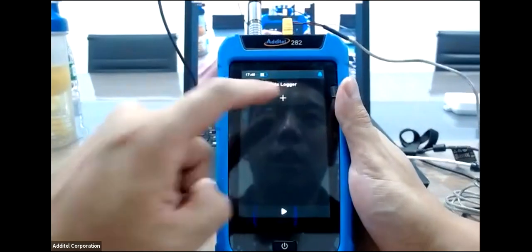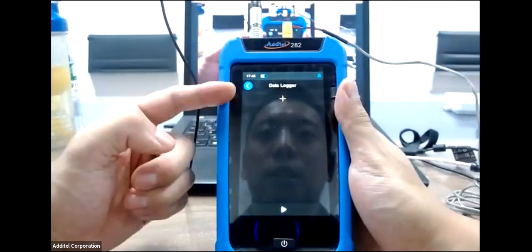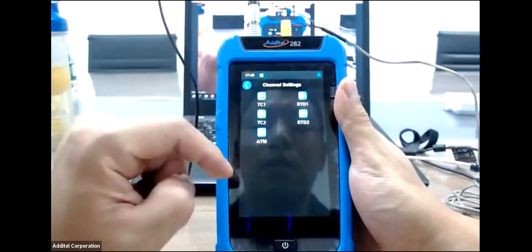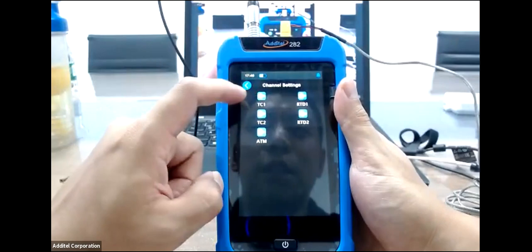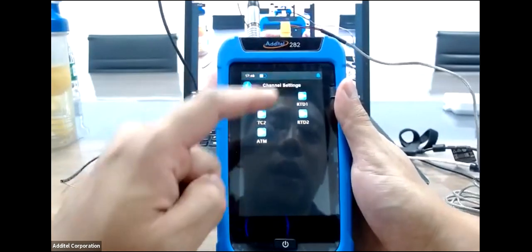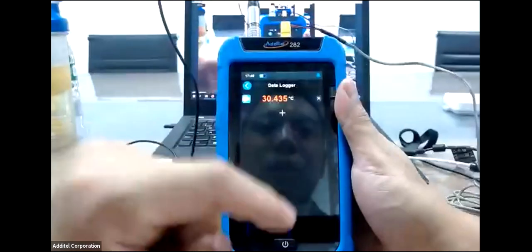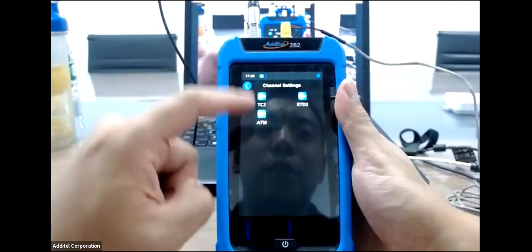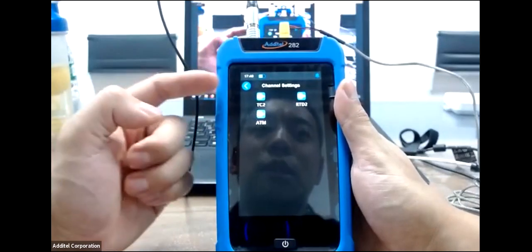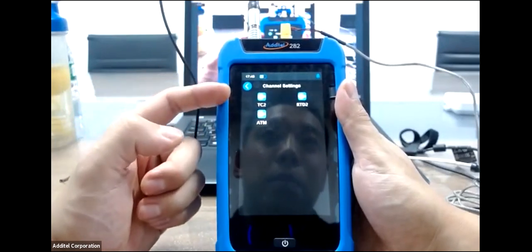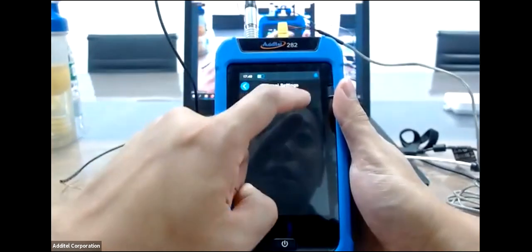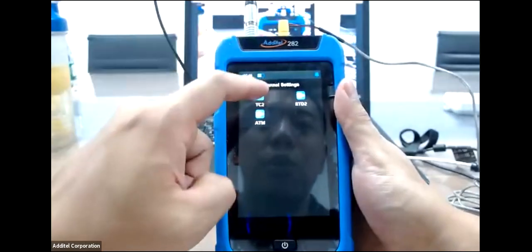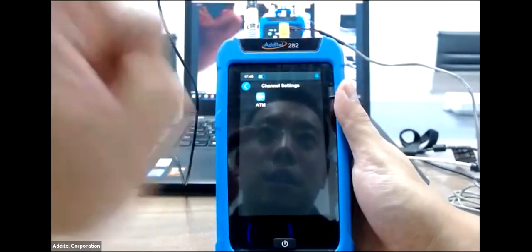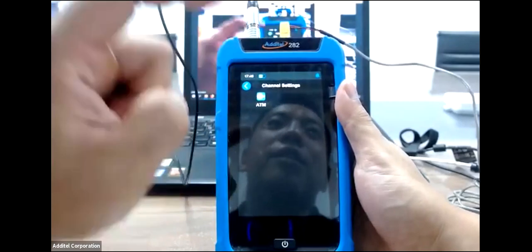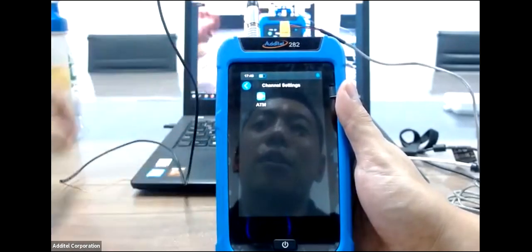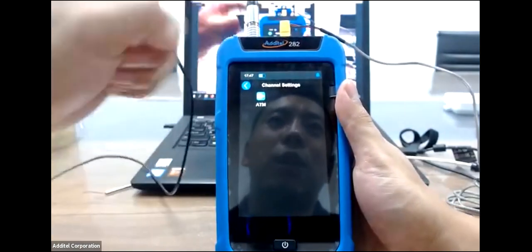For example, since this is the first time we use it, we can select channel 1 as a TC channel 1 or RTD channel 1, for example RTD channel 1. And if you select the second one, you'll see all the channel 1 options disappear, so you can select RTD2 or TC2 as the channel 2 reading. The third one should be the simulated channel for the temperature difference between channel 1 and channel 2.